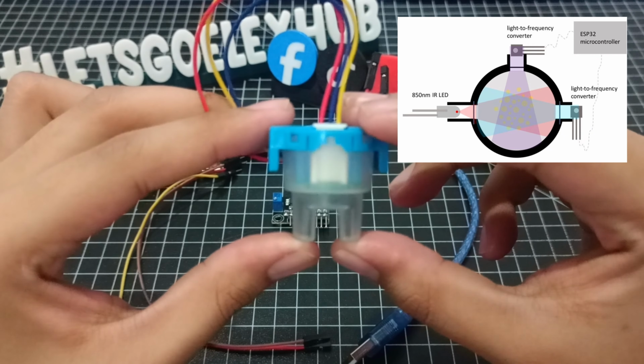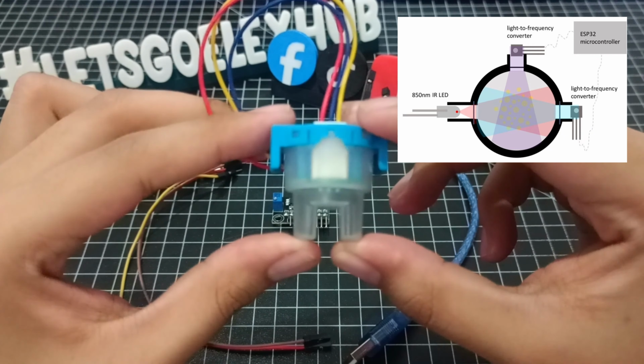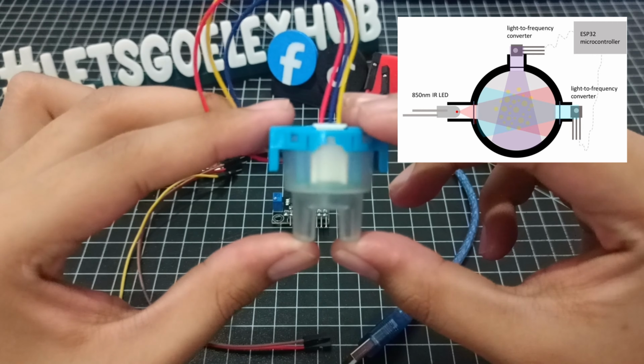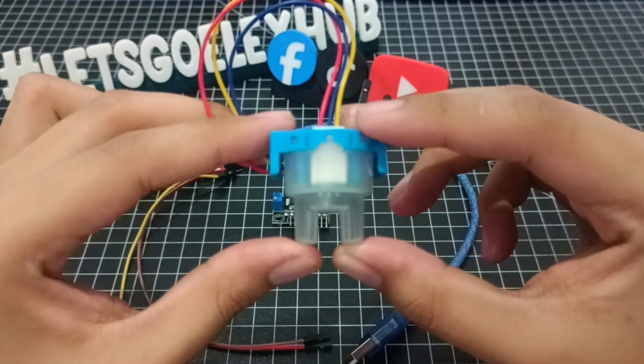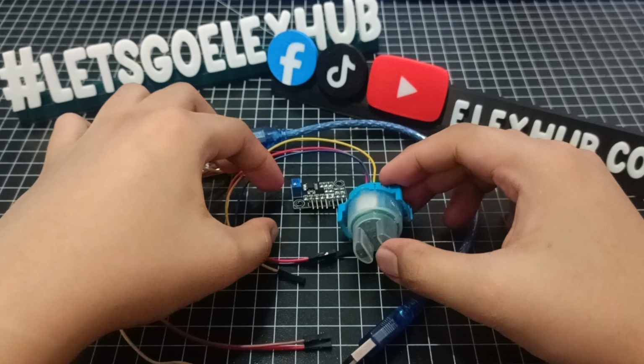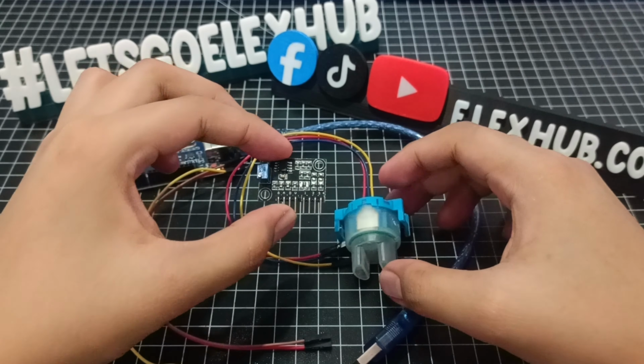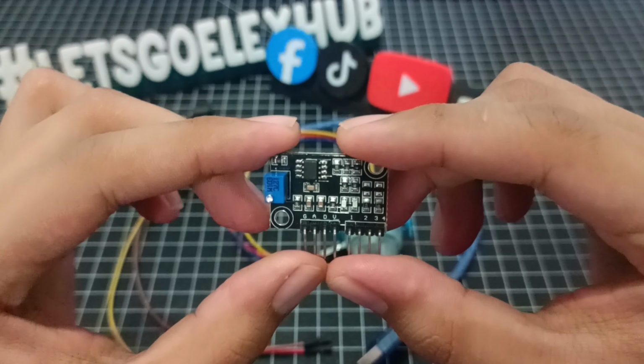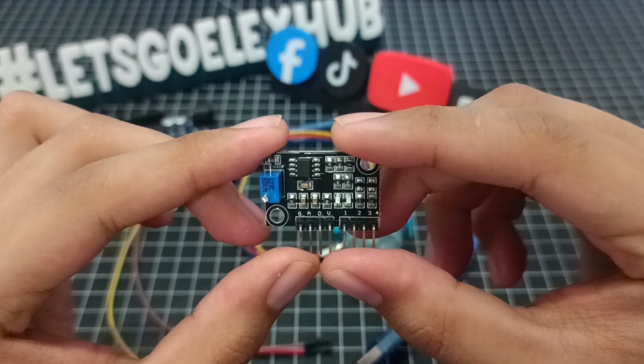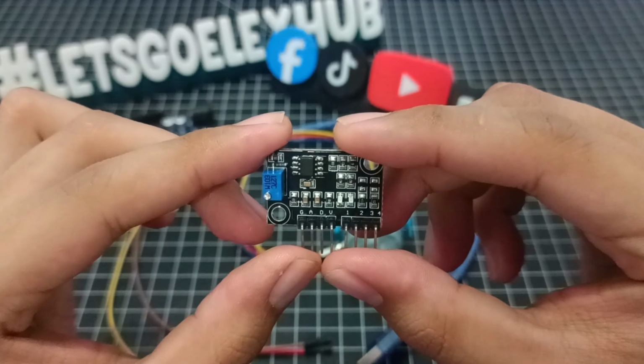The dirtier the water, the less light is transmitted and the sensor produces a current signal that corresponds to the turbidity level. The turbidity sensor module converts the current signal output by the sensor into a voltage signal and performs analog to digital conversion. This comes with two outputs.